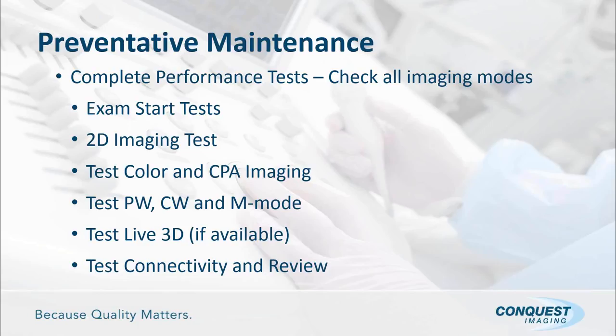So I've listed some specific checks that we want to make sure you cover during this preventative maintenance. You want to start off by making sure you can create an exam. My recommendation is call it exactly what you're going to do. If you're doing an ACR PM, for example, I put my first name as PM and my last name is ACR, and that indicates exactly what specification you're performing this PM to. You also want to do 2D image testing, as well as going into testing color and color power angio on the cardiac systems. You want to test your pulse wave, continuous wave, and M modes, as well as live 3D, if that option is available. Obviously, not all Epiqs come with the ability to do live 3D.